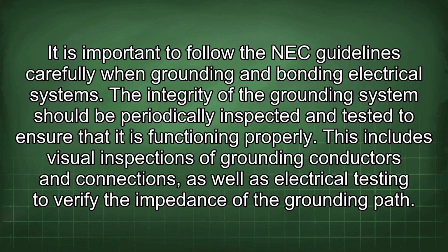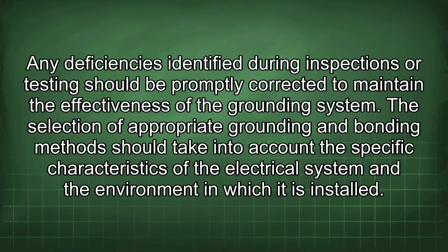It is important to follow the NEC guidelines carefully when grounding and bonding electrical systems. The integrity of the grounding system should be periodically inspected and tested to ensure that it is functioning properly. This includes visual inspections of grounding conductors and connections, as well as electrical testing to verify the impedance of the grounding path. Any deficiencies identified during inspections or testing should be promptly corrected to maintain the effectiveness of the grounding system. The selection of appropriate grounding and bonding methods should take into account the specific characteristics of the electrical system and the environment in which it is installed.